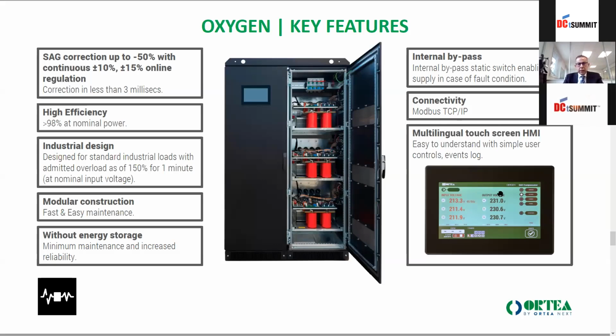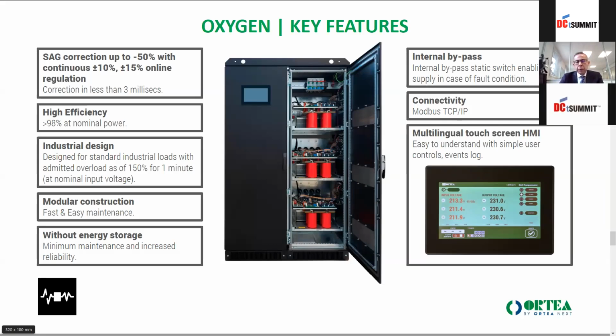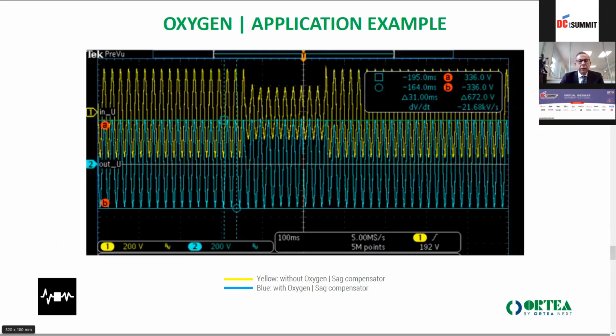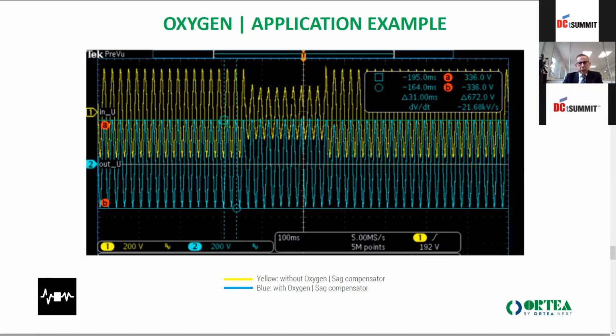units. This allows people also to monitor the touchscreen unit and see what is happening on their SAG compensator. We installed 3 SAG compensators in Zurich airport in Switzerland, and this is protecting the radar systems because they are very, very sensitive. As you can see here, the main line can have, for some periods, a sine wave SAG. You see the input is in yellow, and the output is described in blue. So it will be always steady.